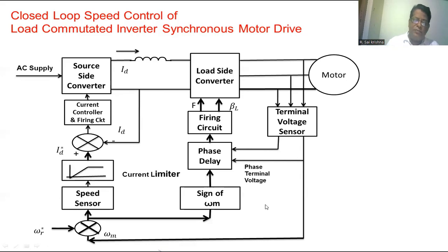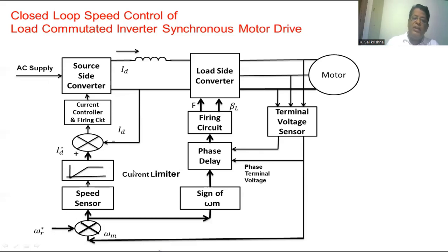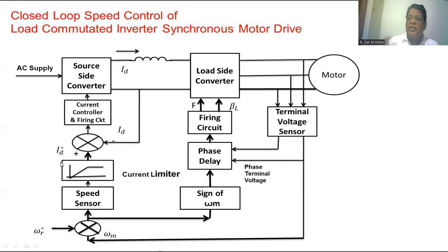If we increase the reference speed, the actual speed is less than the reference speed and the speed error is positive. Based on the sign of the speed error, the commutation advance angle will be set for motoring operation. Since the speed error is positive, the commutation advance angle becomes positive and the load side converter operates accordingly. For the source side converter, the current limiter limits the DC link current to the maximum value because the speed error is positive. This means maximum torque is developed in the motor, so the motor speed accelerates quickly and reaches the desired value. Once it reaches the desired value, the current limiter action reduces and the DC link current decreases, settling to a value where the developed torque equals the load torque.